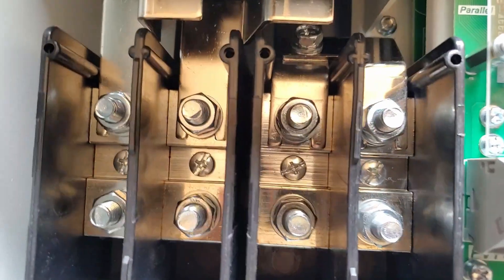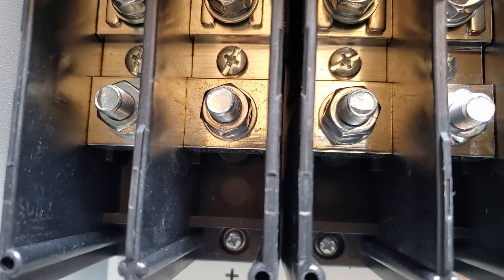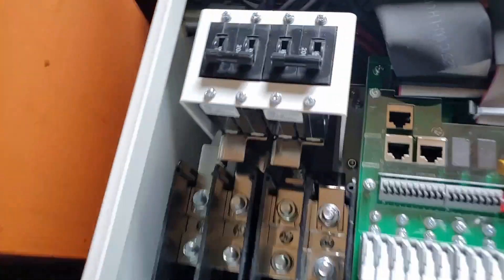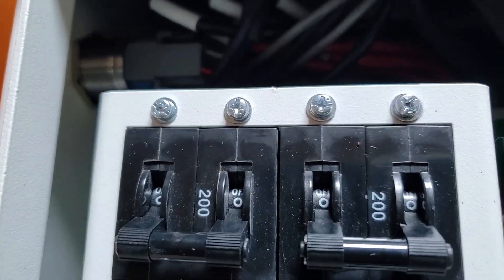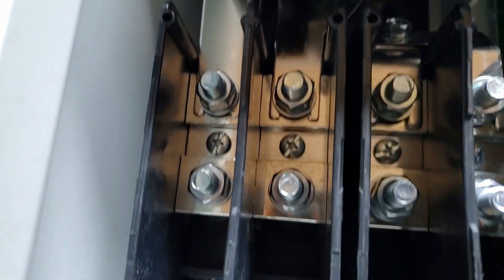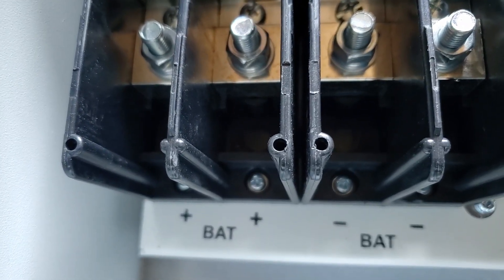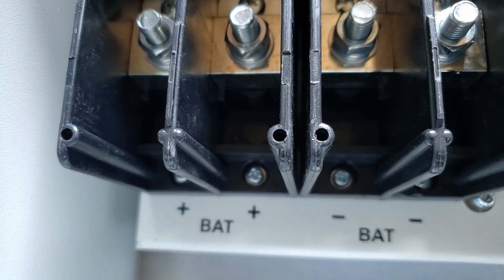That's your common bus bar. And then on this side, we're looking at the DC side — and similar to Victron, they're giving you two positives and two negatives. On the battery side, they gave us a 200 amp breaker — two of them. Very much similar to what you see with the Victrons: two battery positives and two battery negatives. Pretty impressive.